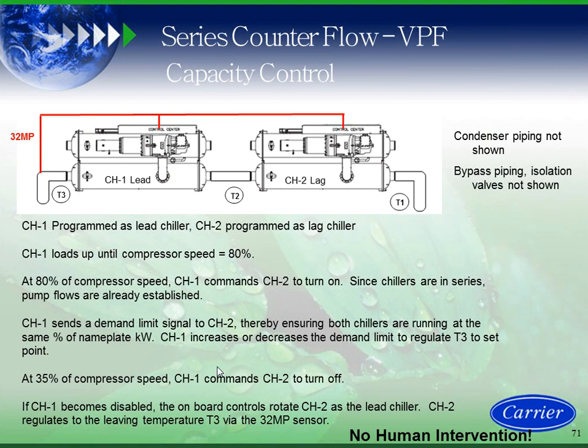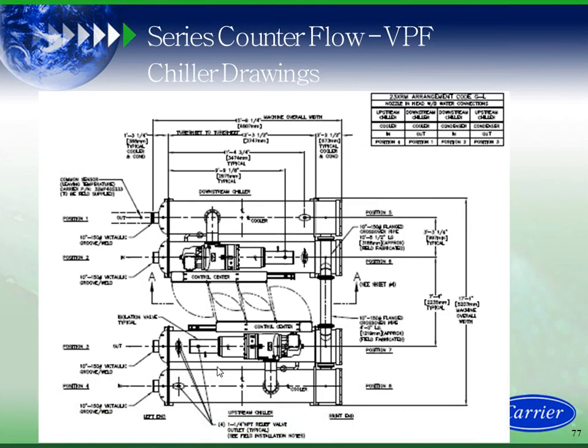What I do recommend when we do a series counterflow plant is we have some bypasses for chill water. So if for some reason one machine has to be serviced, you could still run flow through the other machine. And here's a series counterflow drawing just for your reference. If you have a project and you want some specific drawings on your machine, just contact either your salesman or you can contact myself directly.